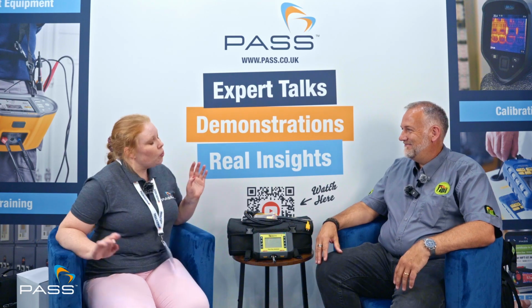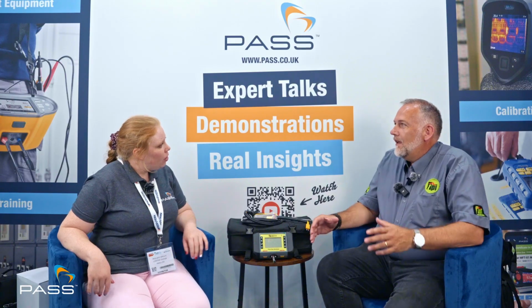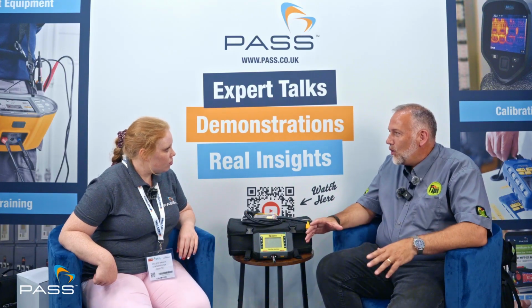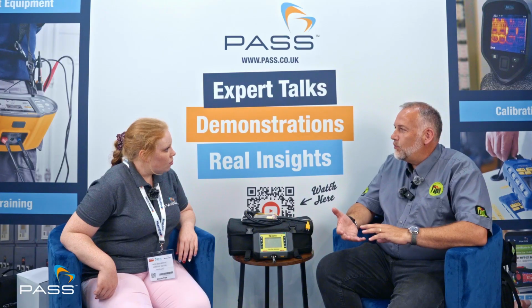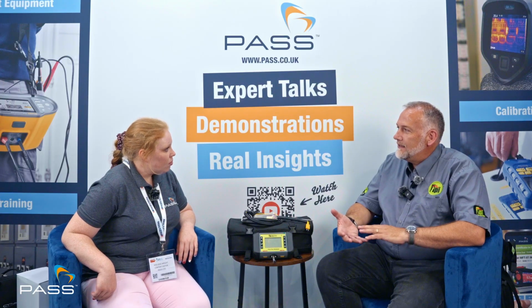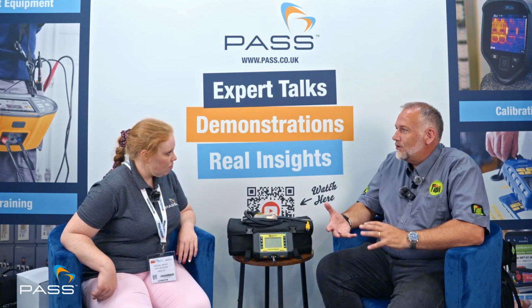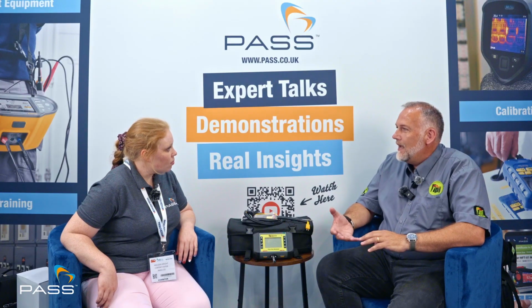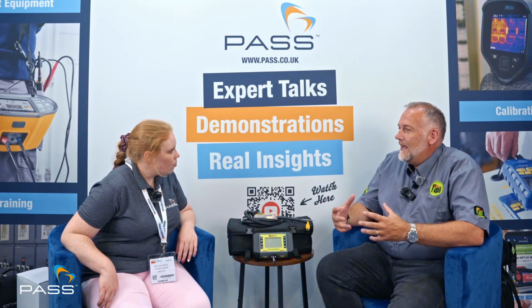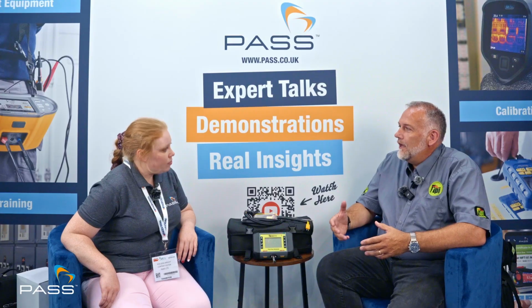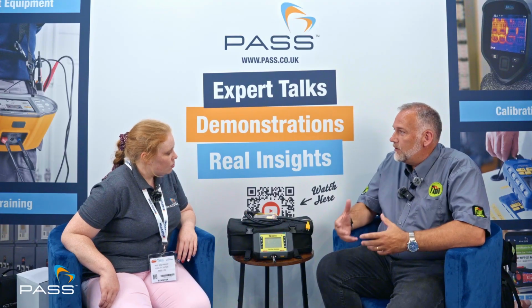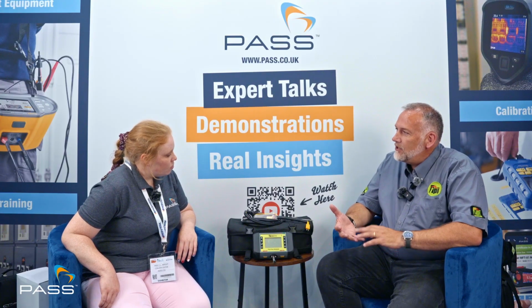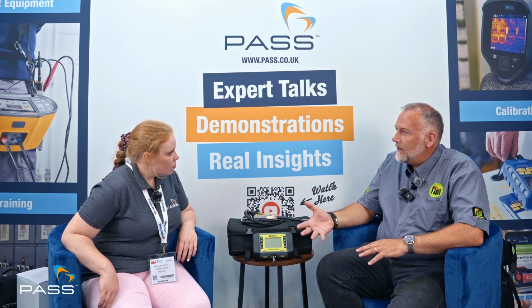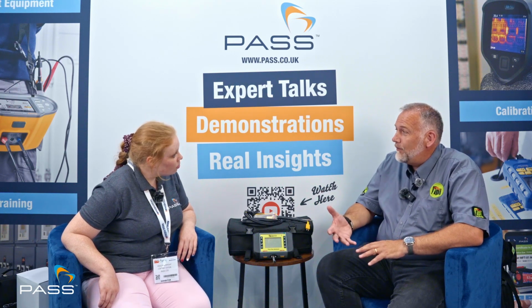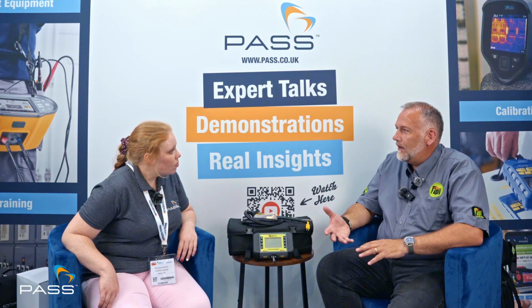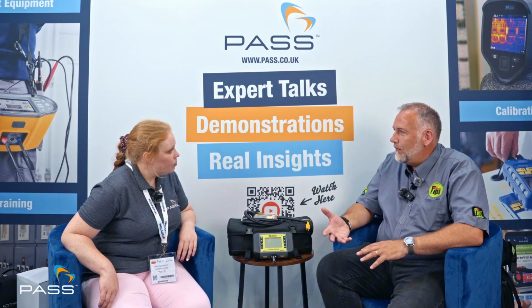So Nigel, what are your tips? Flue gas analysers all work, but you have to remember what we're taking from the boiler to get readings so an engineer can tell someone they're safe to live in that premises. There's moisture, condensation, it's very wet in there. We've got a pump because we want all that sample, but if engineers don't look after their analyzer and probe, it doesn't matter what brand, it's going to get inside. Water and electronics don't mix.